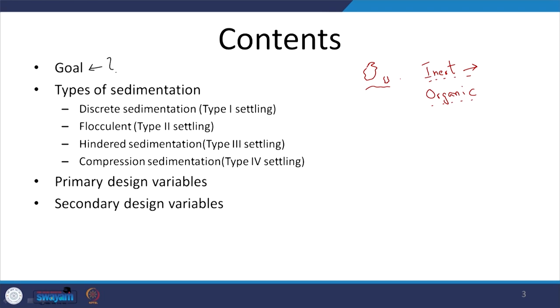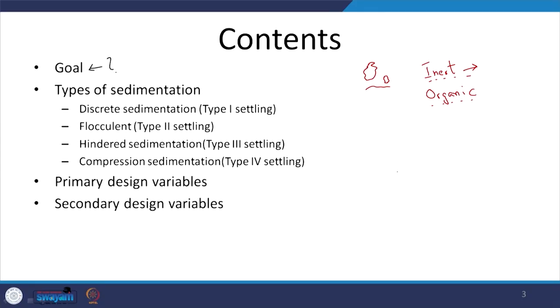Organic content is typically removed by a biological process where microbes in the presence of oxygen catalyze oxidation of our waste — our waste is the microbes' food. The kinetics is improved by enzymes released by microbes, but oxygen needs to be supplied, so we pump air into the relevant biological process, which is costly. If sludge treatment is available, you can remove a significant fraction of organics during sedimentation to reduce the load on the biological process and bring down cost, though other aspects must also be considered.